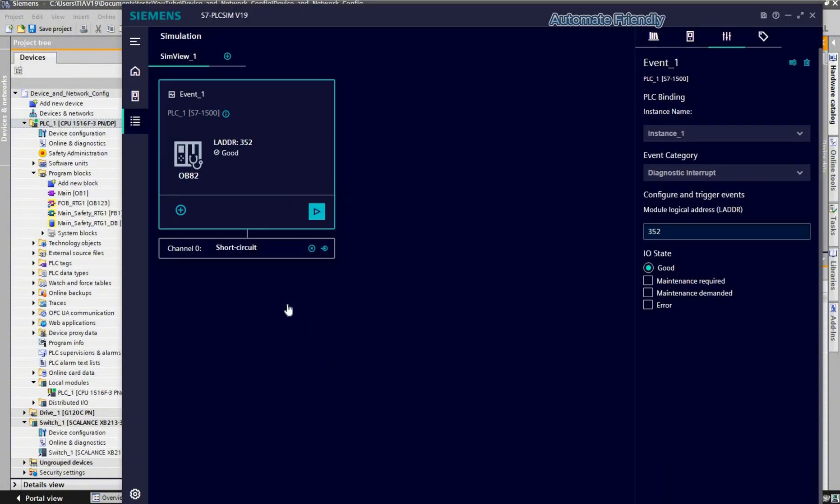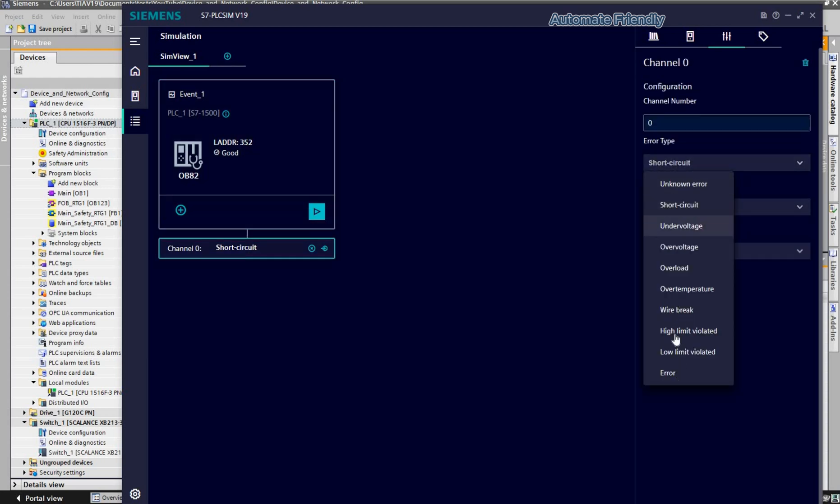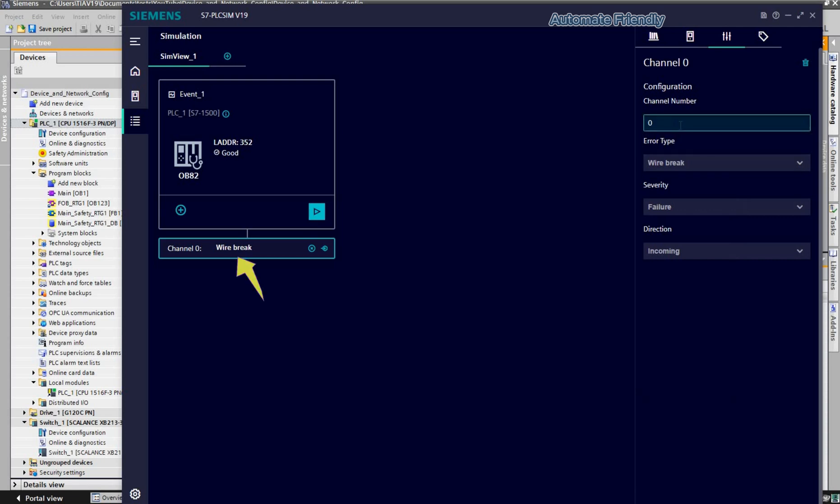Also, by selecting on the channel, we can define the type of the diagnostic event, either a wire break or a short circuit or an under voltage. I can also define the channel number the event should be triggered on.